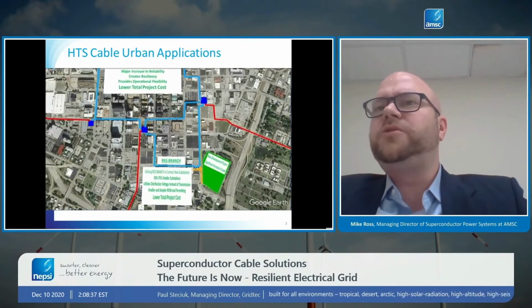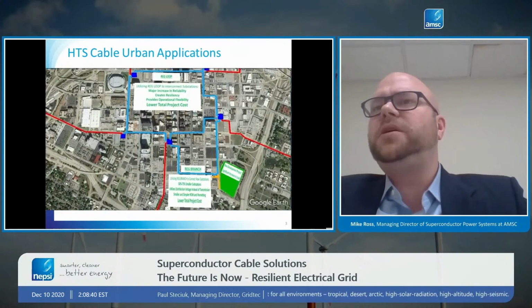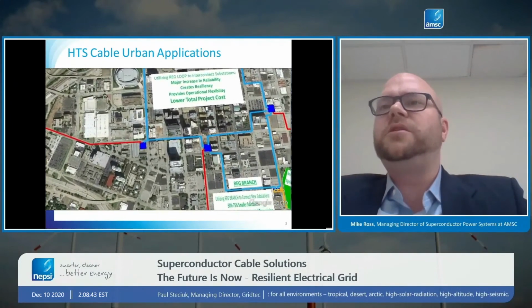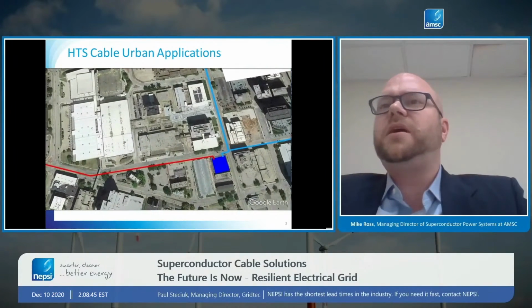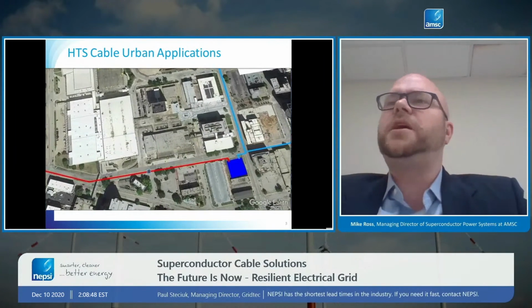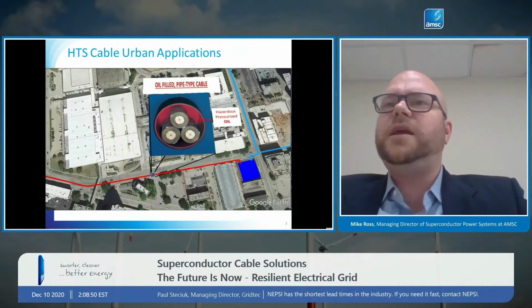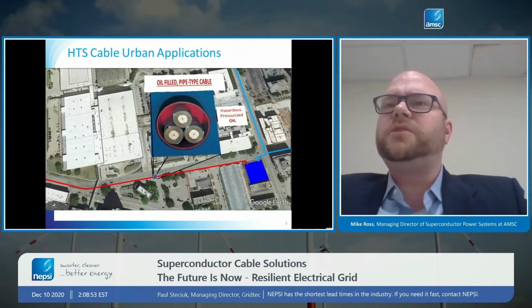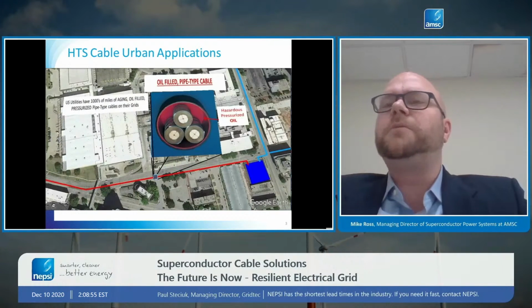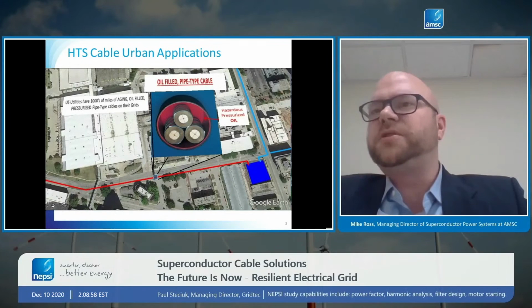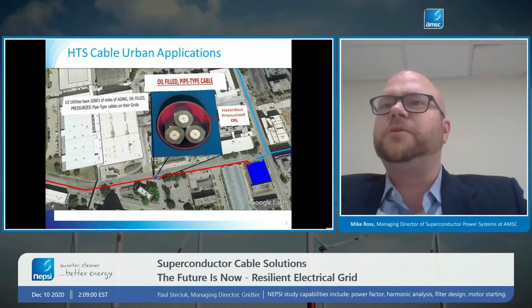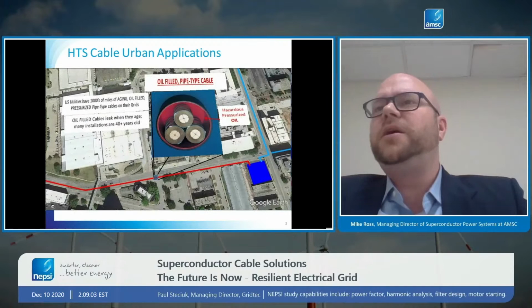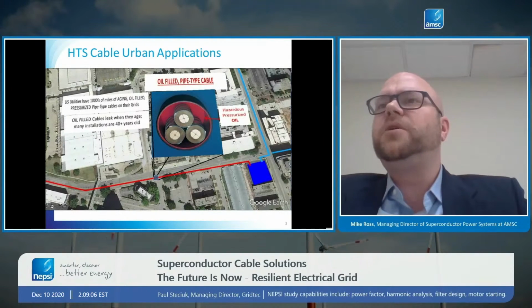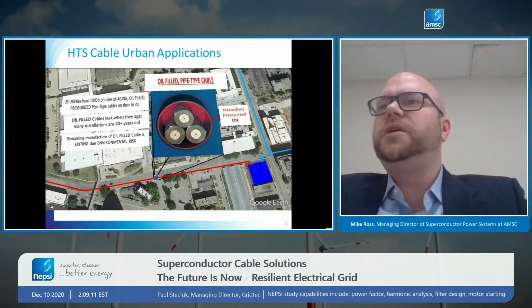So those are 2 main applications. One is increasing reliability, and another is increasing the ability to serve new loads. A third application of superconductor cables in urban areas is this: today, the bulk of U.S. urban areas, the majority of them, use something called pipe-type cables, or high-pressure fluid-filled cables, or oil-filled cables. Those are all terms for the same kind of cable. Here's a picture of what one of those looks like. So what we do in urban areas is we're putting these oil-filled cables in order to move bulk power around.